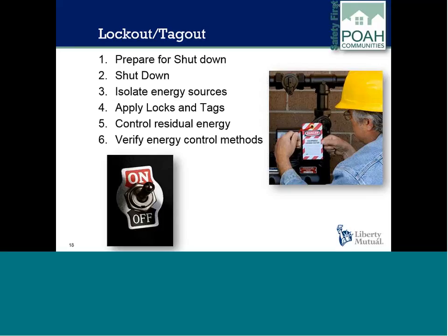Step 5, control residual energy. Release, restrain, or dissipate energy. Prevent the reaccumulation of energy. Isolate the space, blind the lines, disconnect and misalign the lines, double block the valves, and bleed the residual materials. Step 6, verify energy control methods. Assure that switches, valves, and other mechanisms cannot be turned on. Activate equipment control switches and levers and depress start buttons to assure the power is isolated. Return switches, levers, and buttons to the off position. Use a meter to assure that electrical energy is not present.